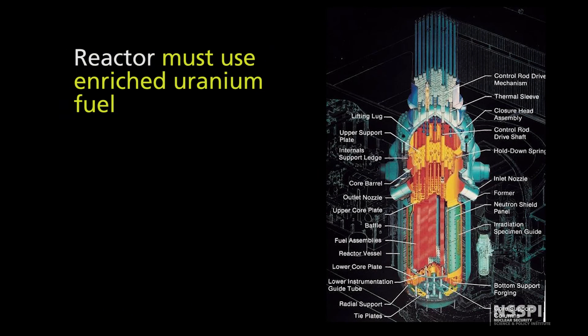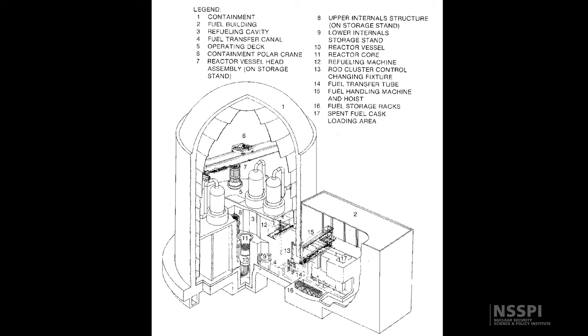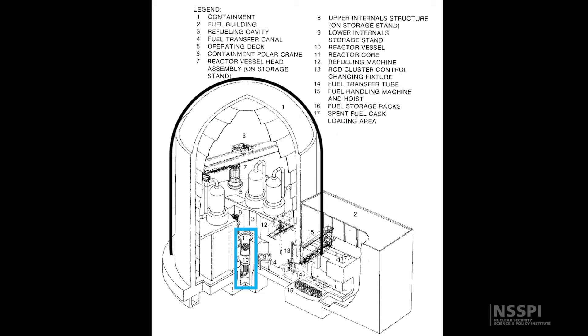Since the PWR uses light water, it also has to use enriched uranium fuel. This picture shows the typical Westinghouse-style PWR reactor. The containment structure shows the reactor as the small component in the center, with the large structures being the steam generators. Containment around the outside is there to provide safety so that if anything bad happened inside the reactor, it would all be contained inside this large concrete and steel structure. Also shown is the spent fuel pool, where spent fuel from the reactor is stored in a separate building outside of containment.